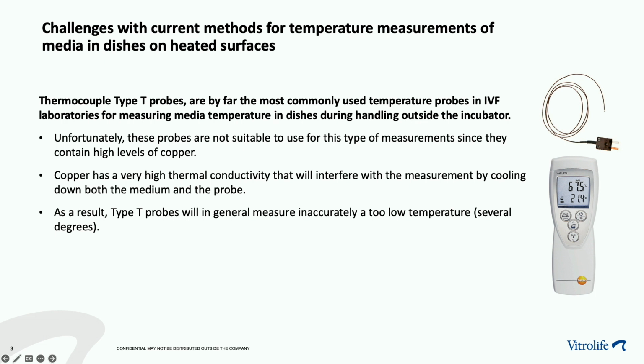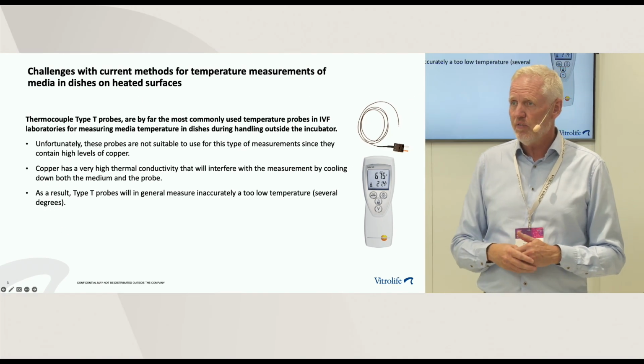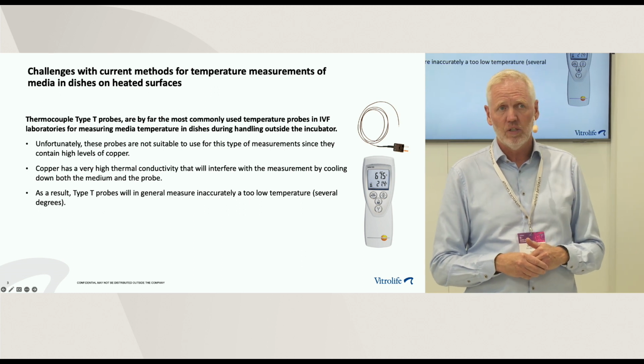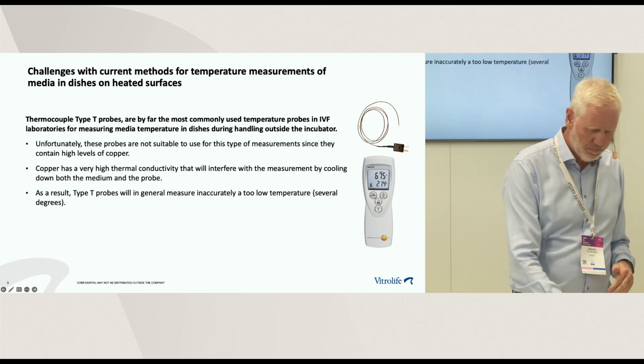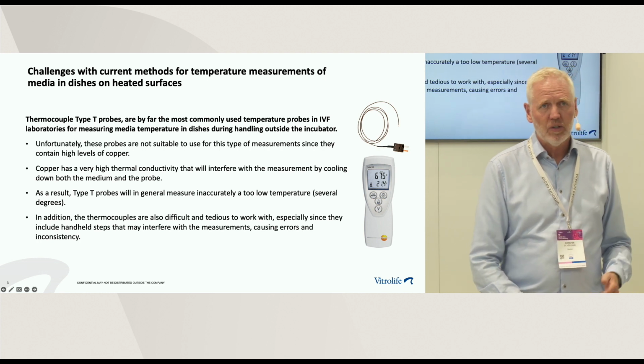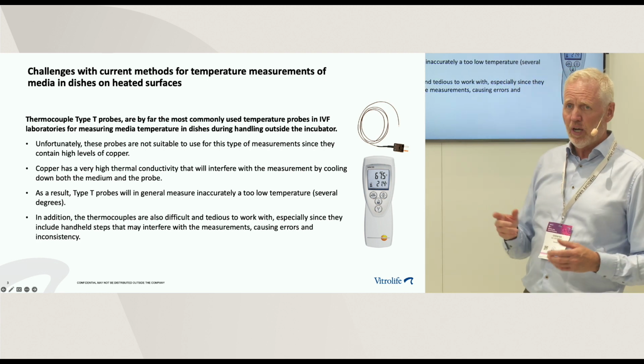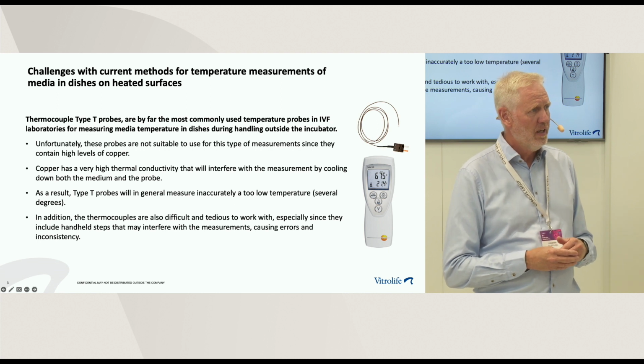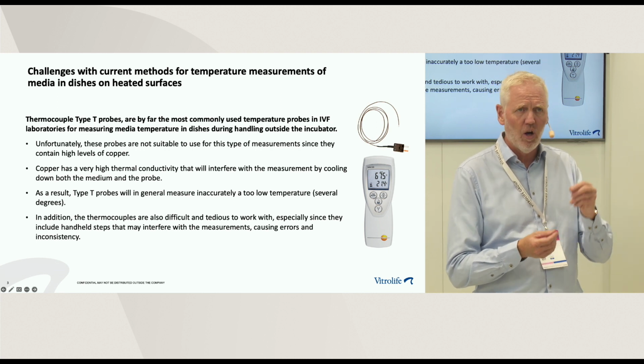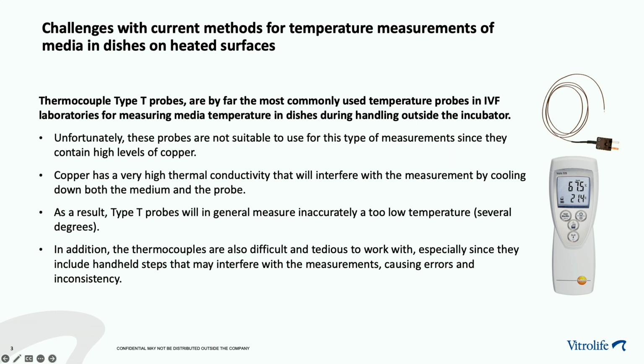So, as I say, type T probes will in general measure inaccurately, too low a temperature, and I'm talking about several degrees. The effect of this in the embryo lab, when you use a thermocouple type T, is that you will increase the temperature until you reach 37, but in fact you will be far above 37, and that is not good for the embryos. In addition, I can also mention that working with these sort of thermocouple probes is not very easy. It's time consuming, they're tedious, they're hard to handle, and there are methods that are much easier to work with.